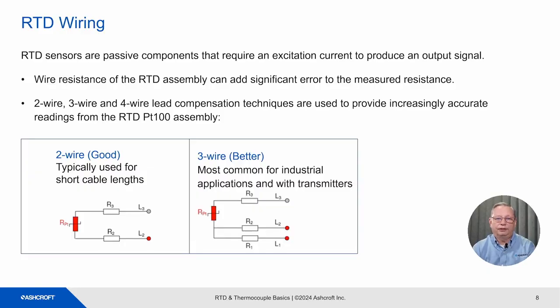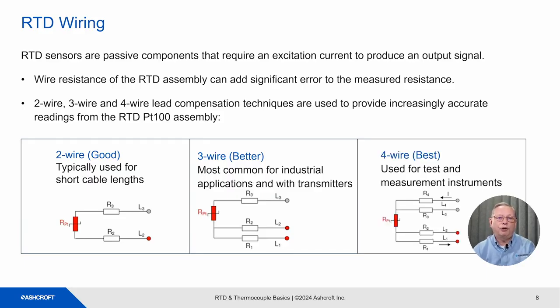3-wire method is better. If the 3 wires are all the same length, you can cancel out the lead wire resistance in the bridge circuit. 3-wire is the most common and is the method typically used with transmitters. 4-wire method is the best and is used for test and measurement applications. Next up is thermocouple basics.